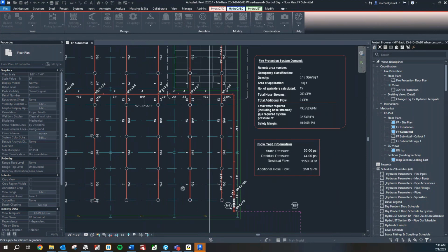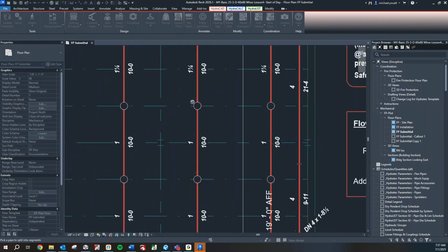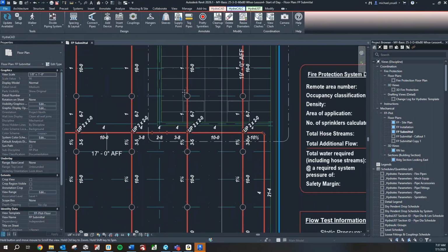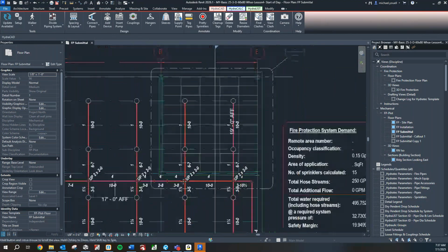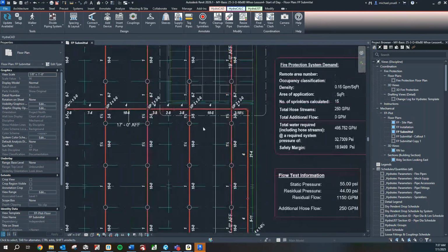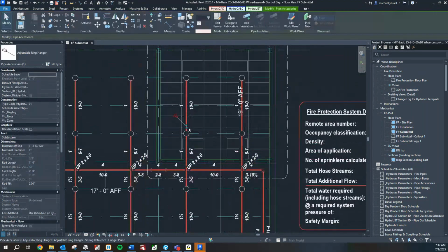Perfect. And now escape, escape, escape. You see it went 6 inches from the end, then it went 10 feet, and 10 feet, and 10 feet. And we didn't get one at the bitter end because 10 feet was beyond that last pipe. So we'd need to stick one more in there. All right.